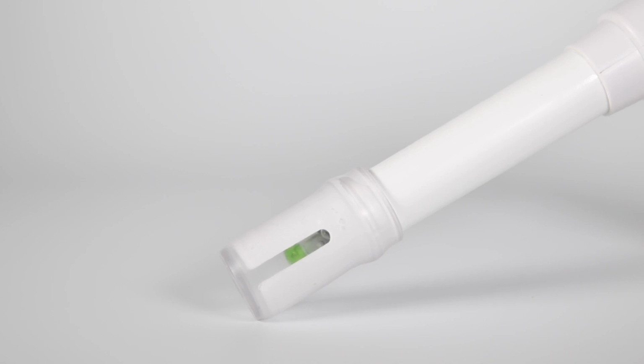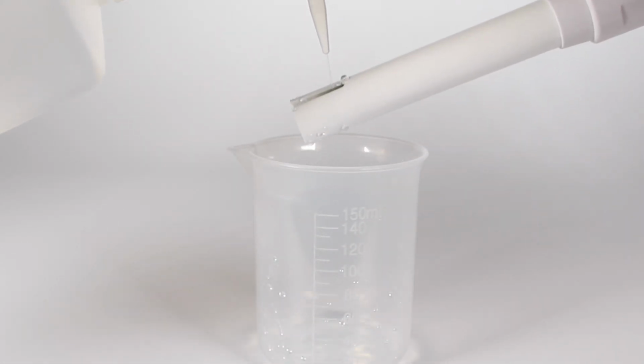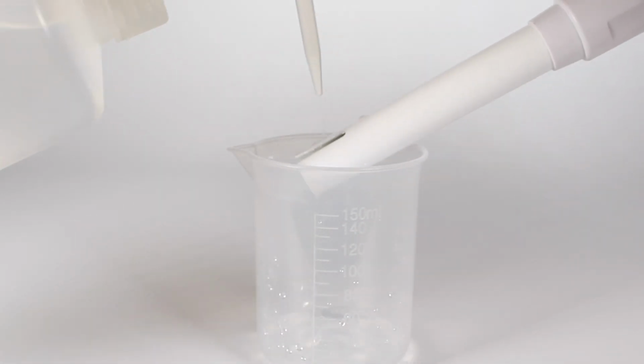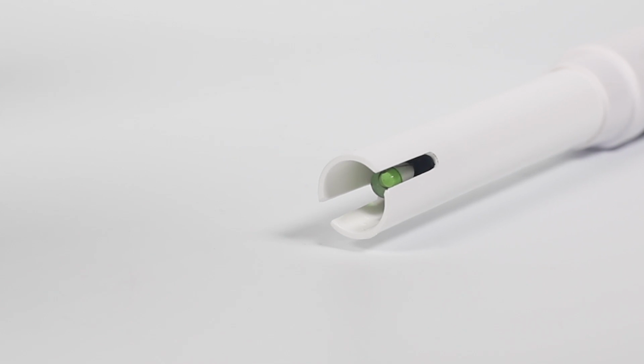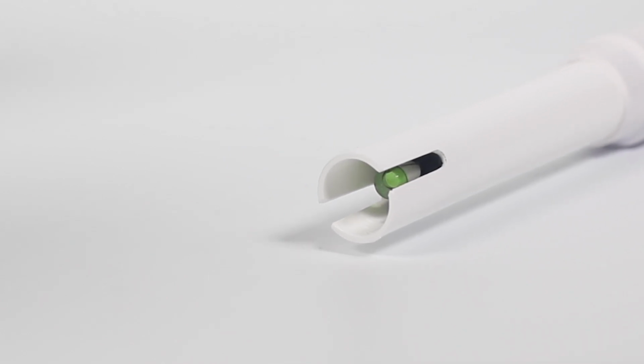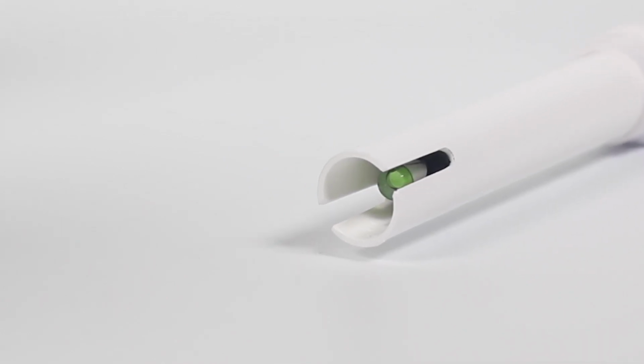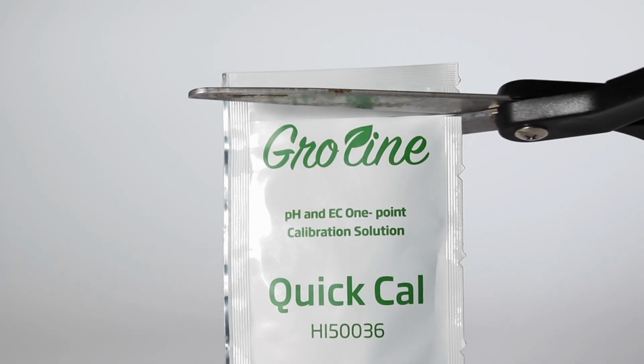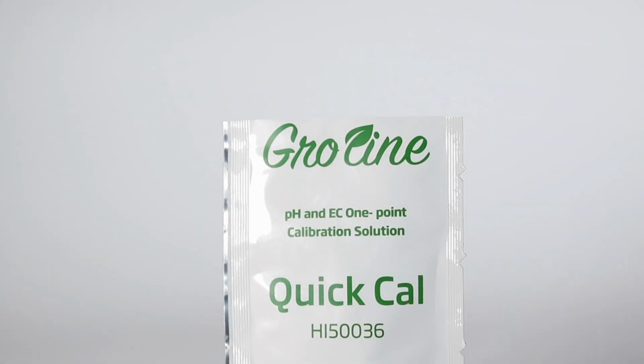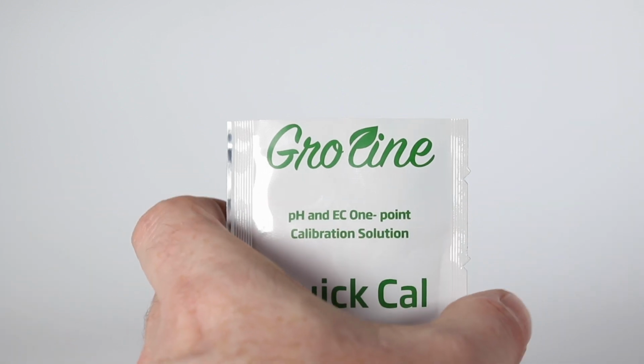The first step of calibration is to rinse. Rinse your probe for 10 seconds with distilled water to dissolve any KCl, potassium chloride crystals left from the storage solution. Tap water is okay if distilled is not available to you. It only takes a small amount of storage solution to contaminate calibration solution. Shake any excess water off of the probe. Do not dry the probe with a paper towel or cloth because this can create a static charge or damage the sensing glass with lint and scratches. Next, open a packet of Quick Cal or pour solution from your bottle of Quick Cal into a small container. Make sure there's enough to submerge the entire glass bulb.